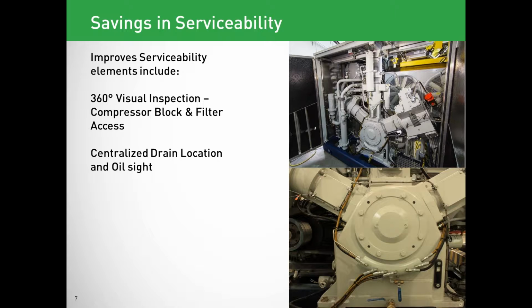In addition, on the right-hand side of the compressor block, there's that black item, which is the oil sight glass. That shows the level of the oil inside the crankcase. It is easily accessible, again, very visible, and allows the operator to keep a much better eye on the oil level, which allows the oil to be topped up on a regular basis as needed and provides much greater visibility, rather than having to crawl inside the package to check the oil level.